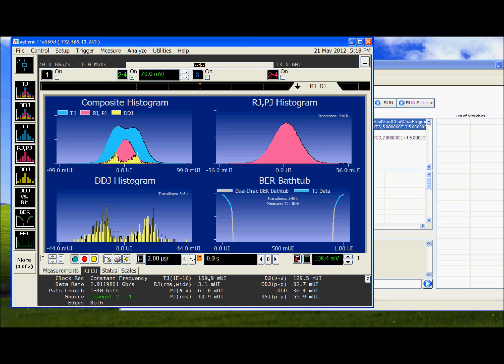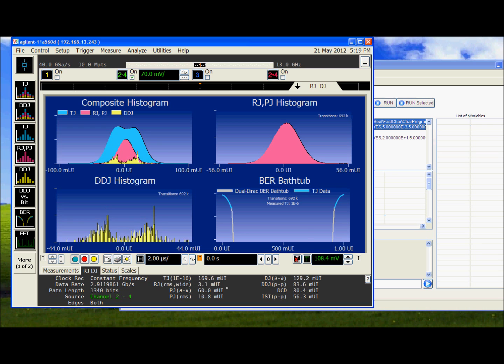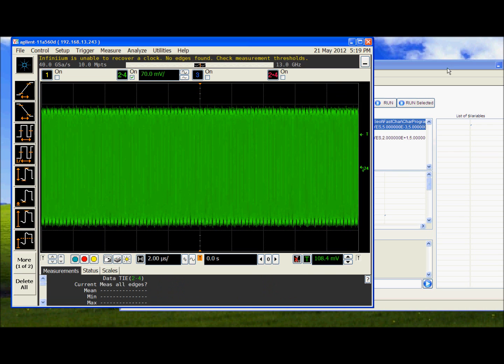The TJ is 167 milli-UI. DJ is 129. And RJ is about 3 milli-UI. Again we have a lot of margin with respect to the spec.